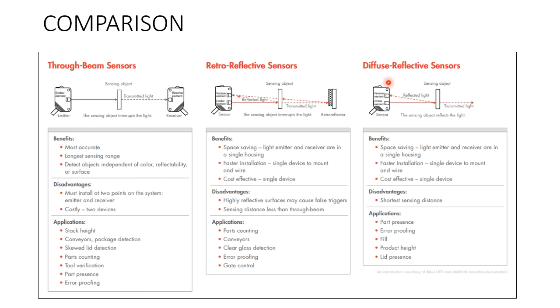The diffuse sensor has the least cost as a single device, but its range is very short compared to through beam sensors which have a very long range. Disadvantages: through beam sensors must be installed precisely and cost is higher. Retro reflective sensors may give false triggers on highly reflective surfaces and have less range. Diffuse sensors have the shortest sensing distance, are affected by surrounding ambient light, and can produce false results.